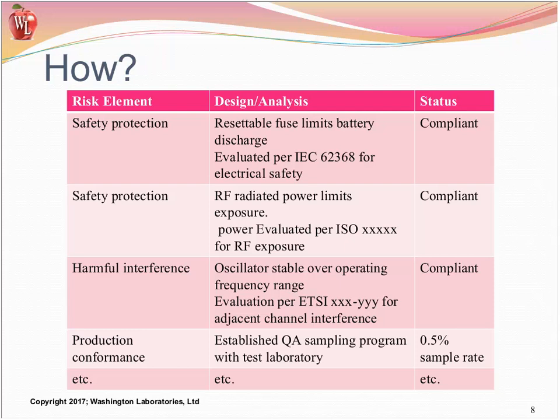And how deep you delve into the safety protection issues varies. A notified body reviewer A may look at it and say, well, you comply with the safety standard, and that's all they want to hear. Another one may say, I want to see the details associated with the safety report in the file. Well, obviously, your file needs all these reports, so it's clearly something you need to produce. And did the safety evaluation cover your particular issue?